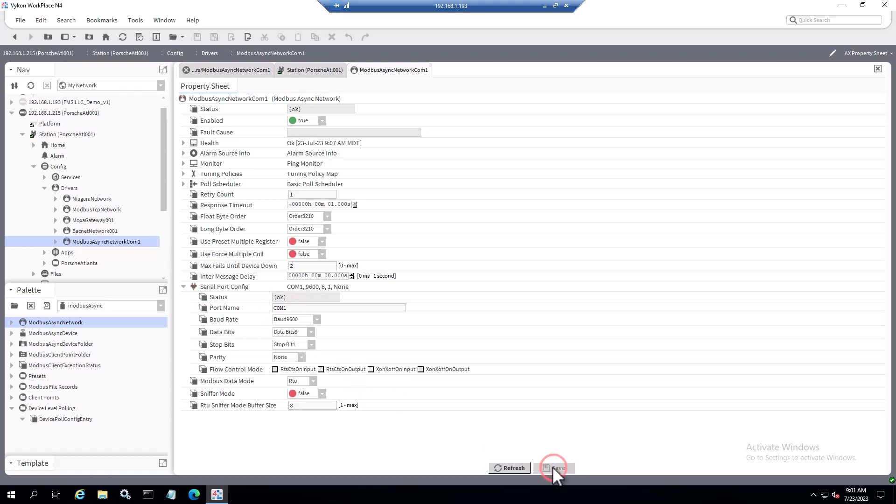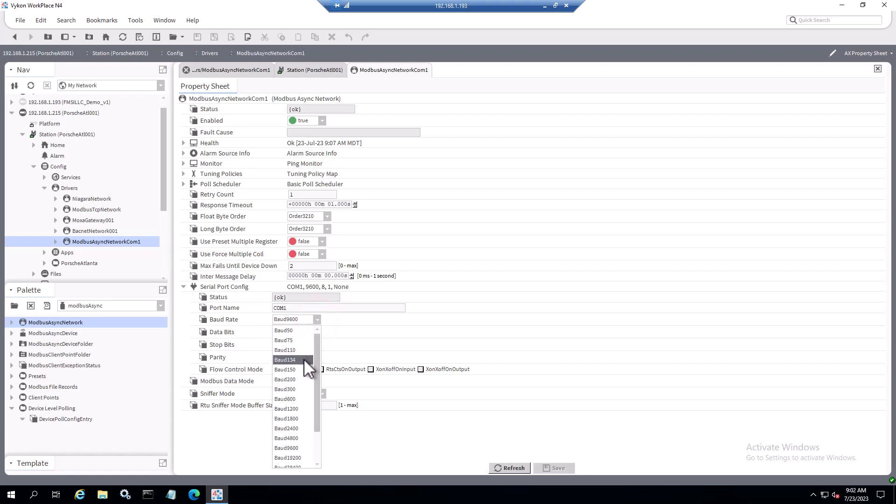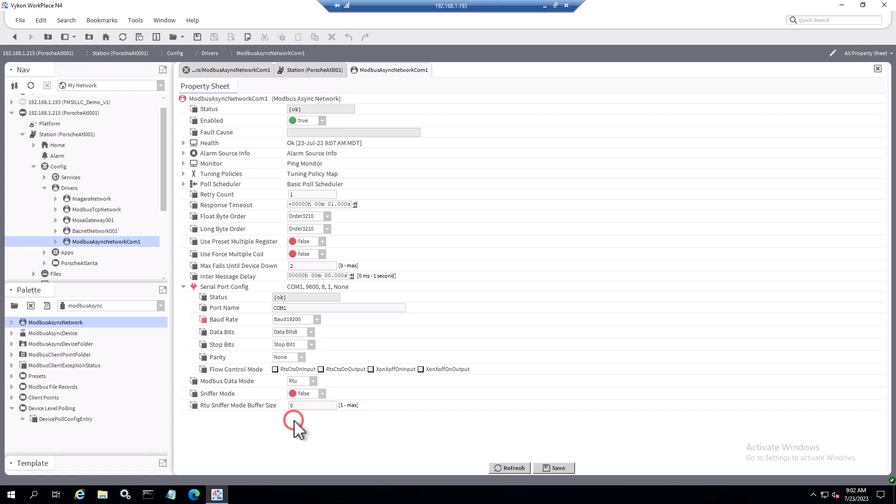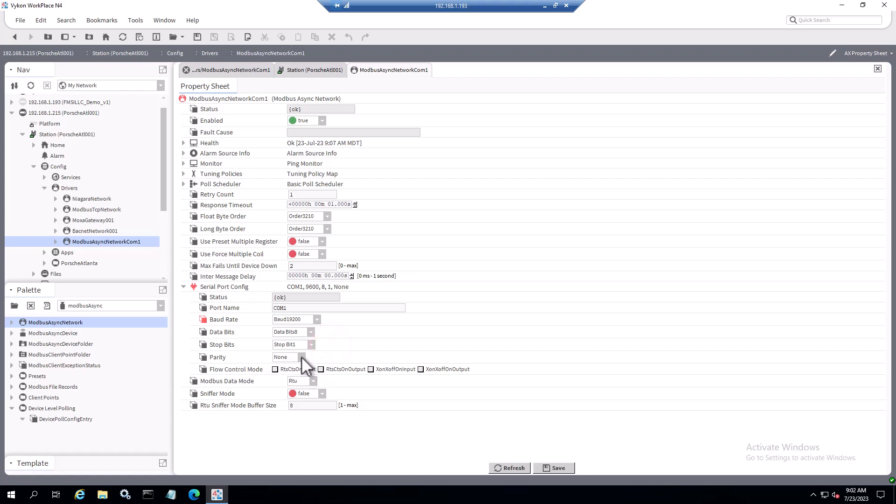Click on save and then we can see our health resolves and we actually have good communications to that port. Then depending on the serial devices you're hooking on to COM1, you want all your serial devices set to the same parameters as far as the baud rate, data bits, stop bit, and parity. Here we go down through Tridium, which gives you about every option when it comes to selecting a baud rate. We're going to select 19200 because that's what I'm using in this application. Data bits eight is correct. Stop bit we're going to be using stop bit one. Parity for this test and deployment would be none, but you can see they give you options of odd, even, mark, and space. Now that we have this COM port configured correctly and we have good stable communications, we're going to hit save.